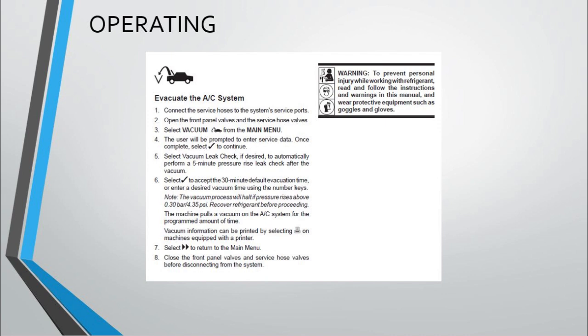4. The user will be prompted to enter service data. Once complete, select to continue. Select vacuum leak check, if desired, to automatically perform a 5-minute pressure rise leak check after the vacuum. Select to accept the 30-minute default evacuation time or enter a desired vacuum time using the number keys. Note: the vacuum process will halt if pressure rises above 0.30 bar or 4.35 psi.